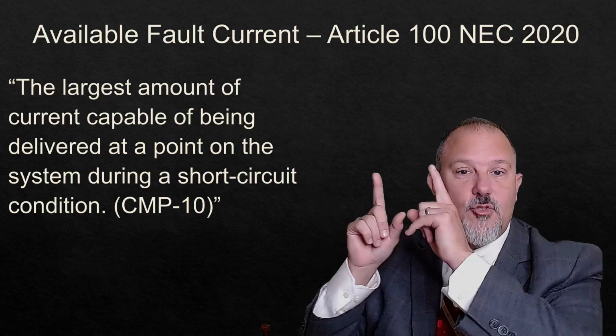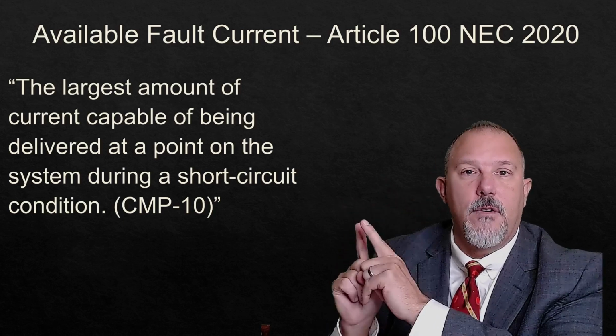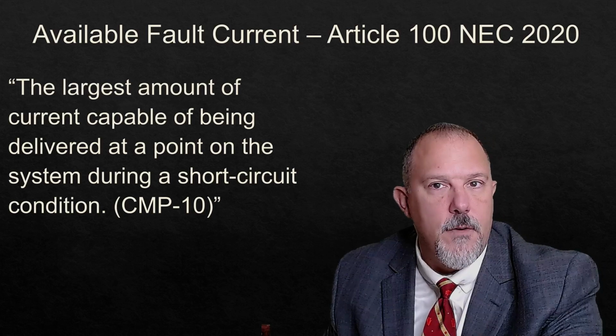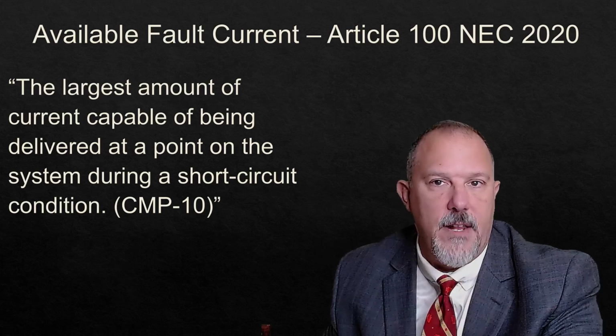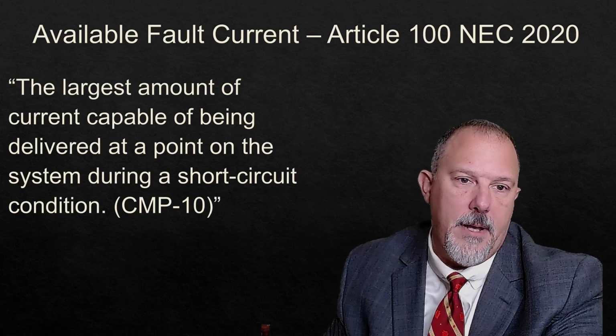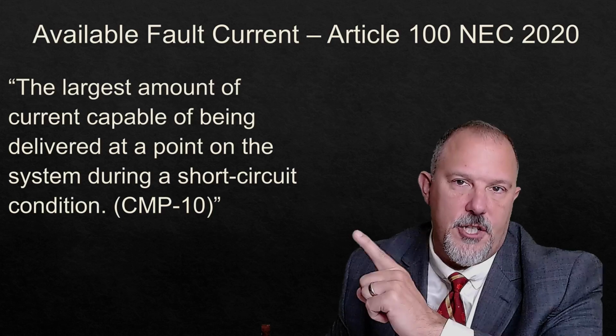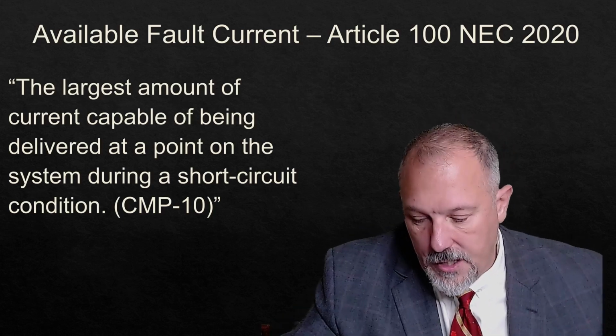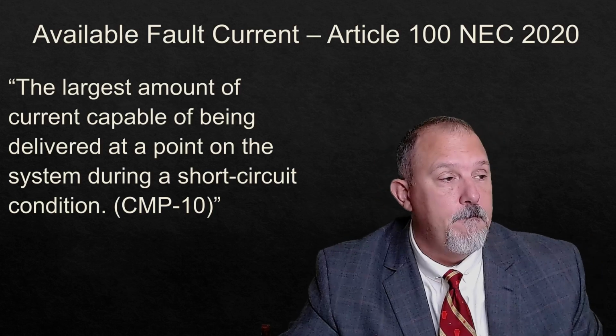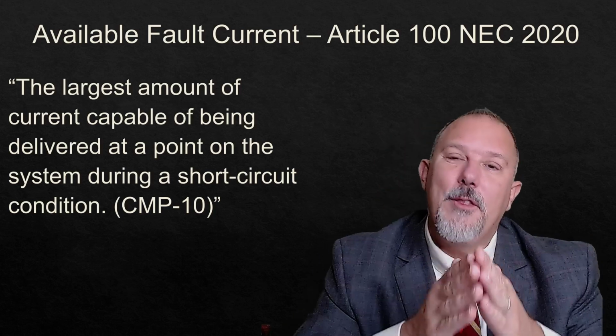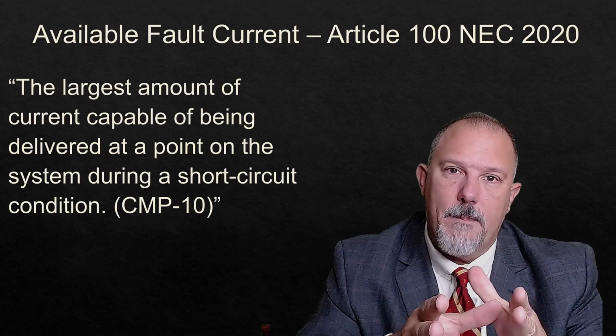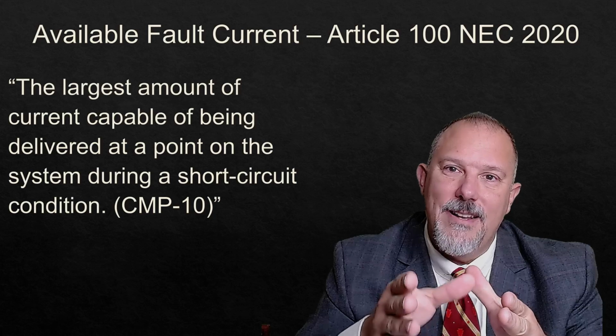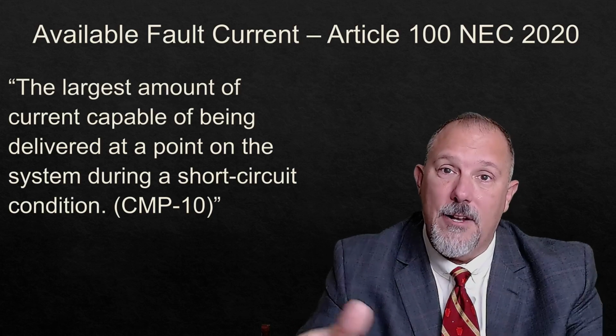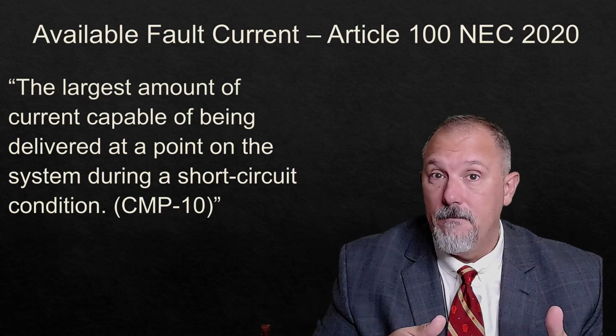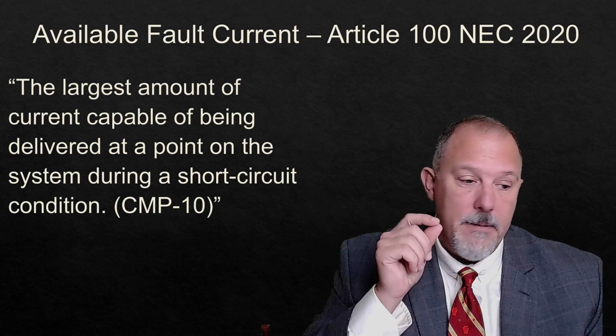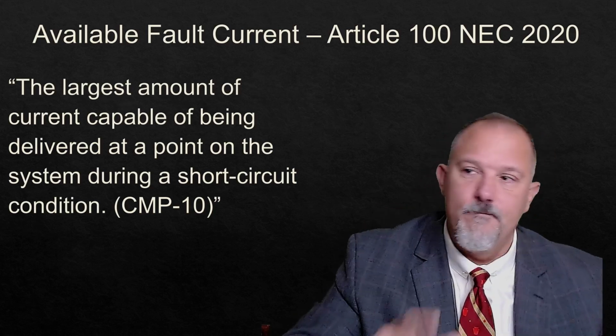Why did they do that? Because it's right here in the definition of available fault current. So all I need to do is say available fault current, and I already know it is the maximum available fault current, the largest amount of current capable of being delivered at a point, because it is in the definition. So it seems like a simple change, seems like a no-brainer change, but it's an important detail to remember. But the other really interesting part about this topic is that interrupting rating does not necessarily mean the maximum available fault current. An interrupting rating could be something other than fault current. That is a maximum amount of current that a component can stop from flowing.